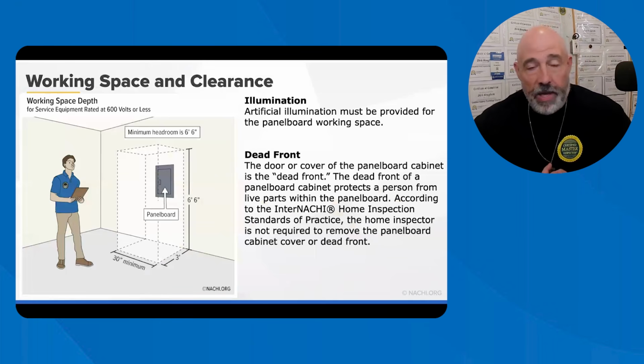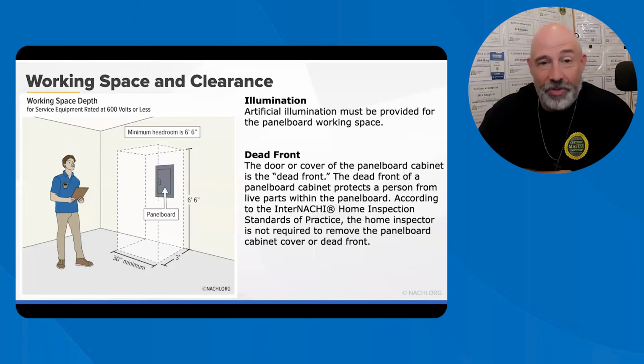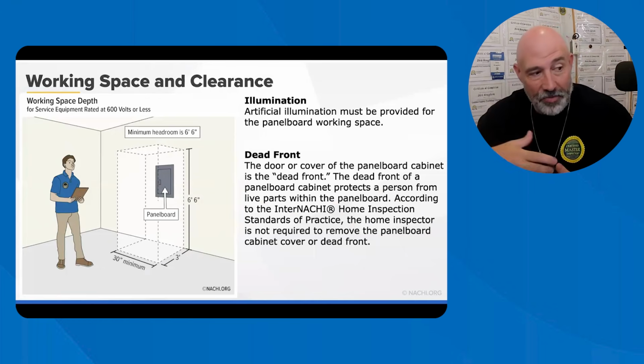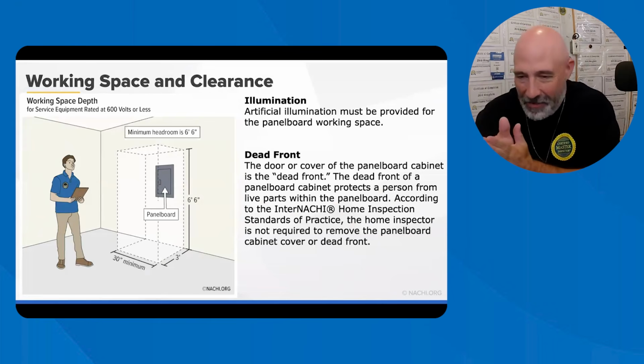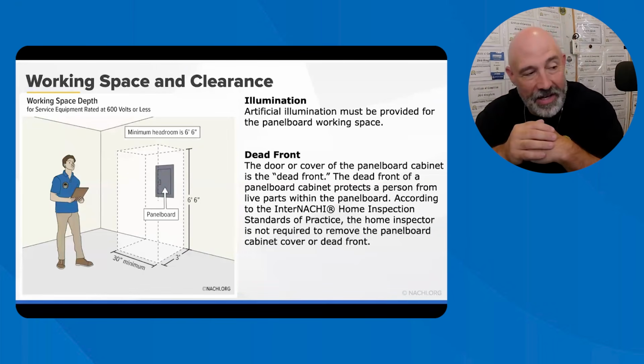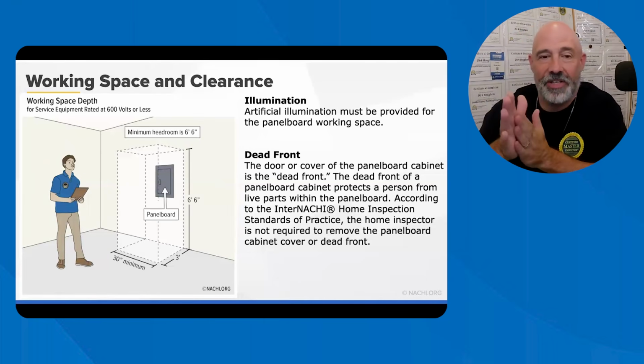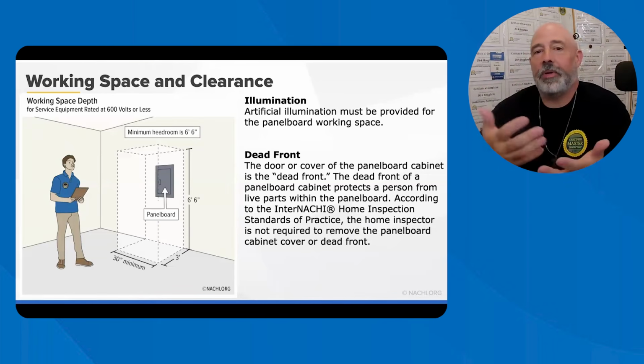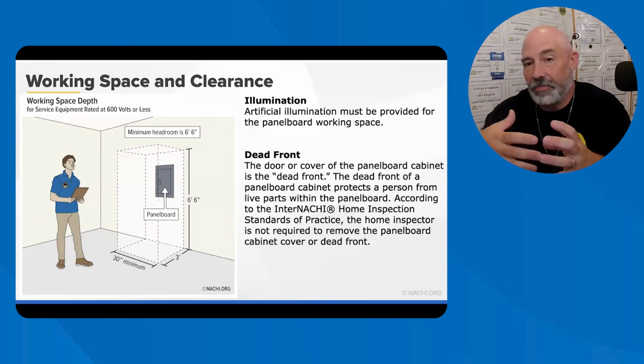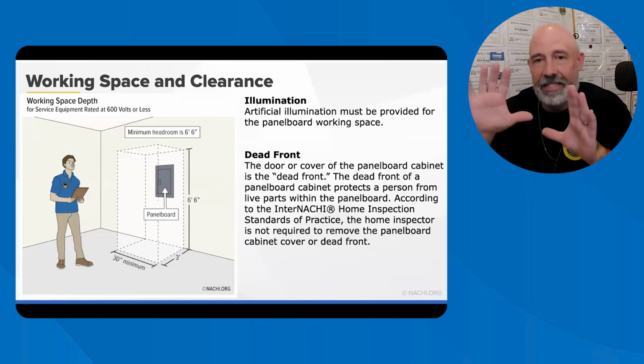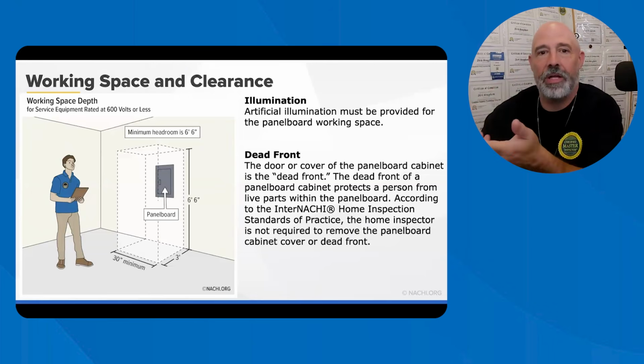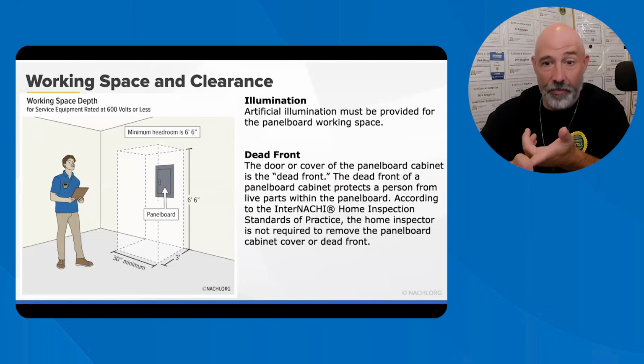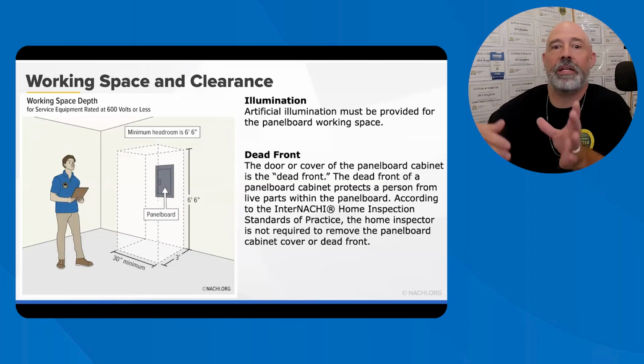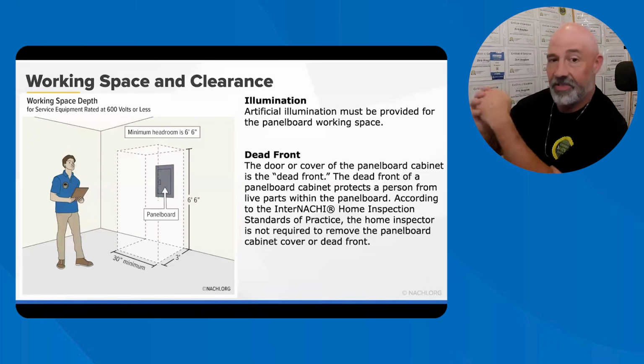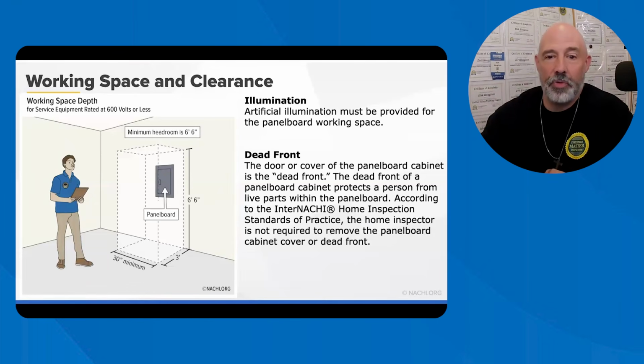Okay. Now, panel board clearance. This is probably one of my most common call outs, which I make at least once or twice a week, just because people will put shelves dead straight in front of the panel or right beside it. They don't have the clearance that they should have. Sometimes I find them in kitchens, with a refrigerator right there. I mean, it's just crazy. Electrical panel boards require adequate working space. This is very deadly equipment, and people don't even respect it. So the general rule is 36 inches of clear working space in front of the panel, and 30 inches of width centered on the panel, so right from the center is 30 inches. And there should be 6.5 feet of headroom in the working area.